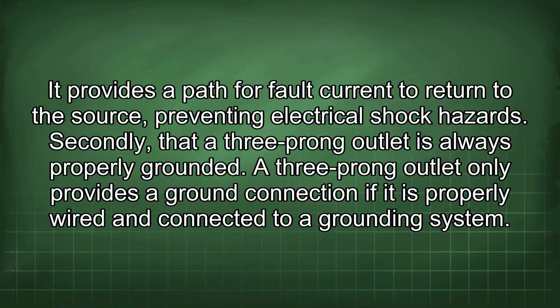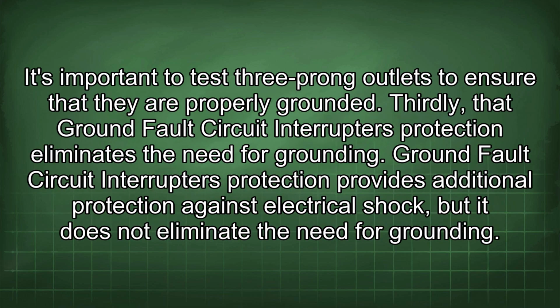Secondly, that a 3-prong outlet is always properly grounded. A 3-prong outlet only provides a ground connection if it is properly wired and connected to a grounding system. It's important to test three-prong outlets to ensure that they are properly grounded.